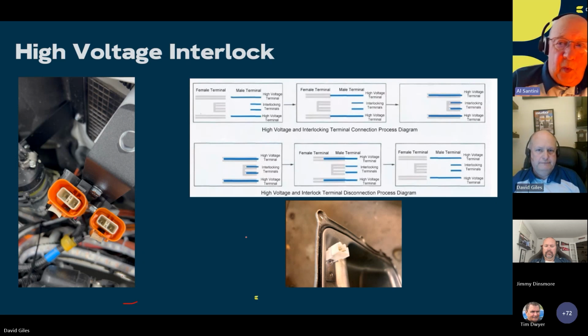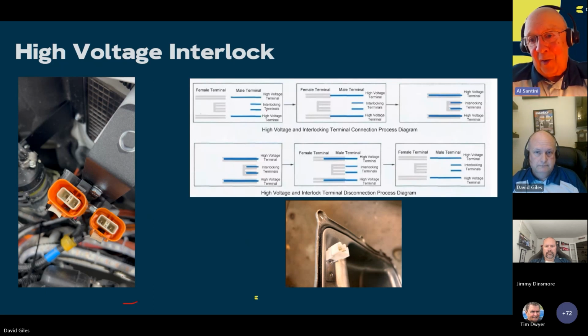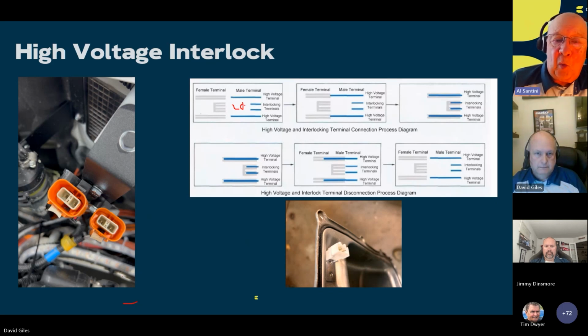We have the low voltage interlock, and part of that low voltage interlock runs through the high voltage connectors. That may sound complicated, but think of it this way: when do we want the circuit to be non-functional, when do we want the system to safely shut down? A, if anything is wrong with the interlock. But B, also if someone disconnects a high voltage connector.